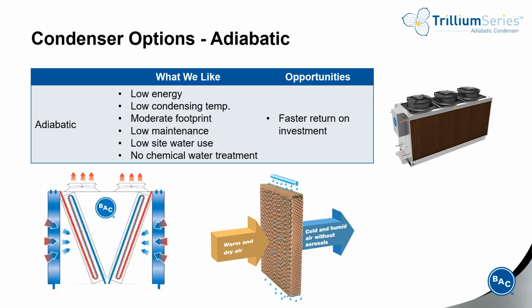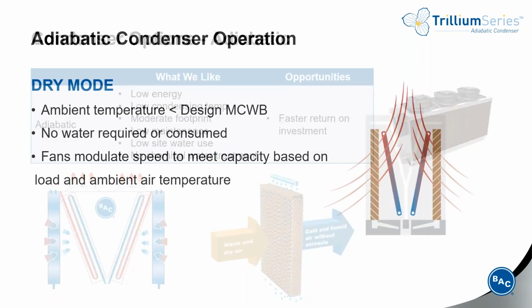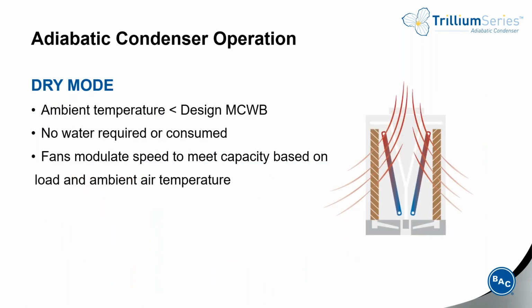Also, they feature small footprints similar to air-cooled condensers, but much lower water use than a similar evaporative condenser, and no chemical water treatment is required with an adiabatic type system. Now let's just look a little bit more at the modes of operation for adiabatic coolers. In its most simple form, it runs in dry mode.